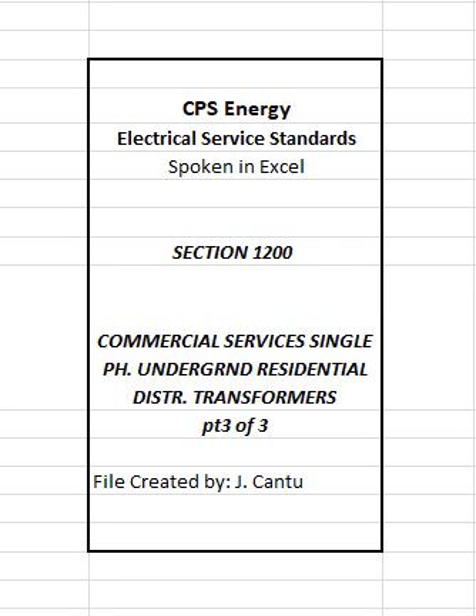1205.4 Service entrance conductors. The maximum number and size of service entrance conductors that may be connected to a CPS Energy transformer are identified in Table 1201 and depend on transformer kVA size. Where customer elects to install conductors in excess of that allowed by Table 1201, the conductors shall terminate in a customer-furnished and installed tap box pre-approved by CPS Energy, see Article 1205.5.